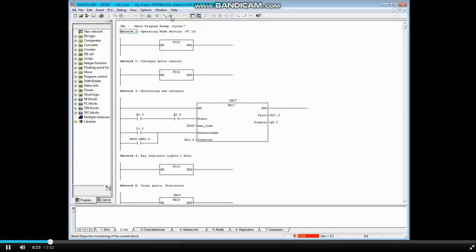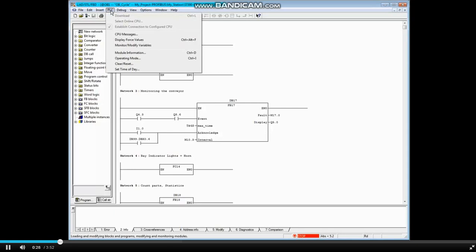You can see that the processor has faulted and gone to the Stop mode. As a general rule, the first place to look when a fault occurs is the CPU's Diagnostic Buffer located in the Module Information tool.